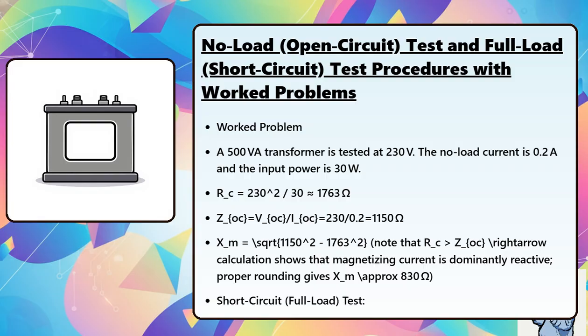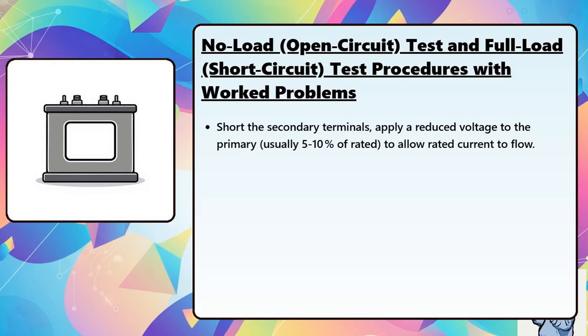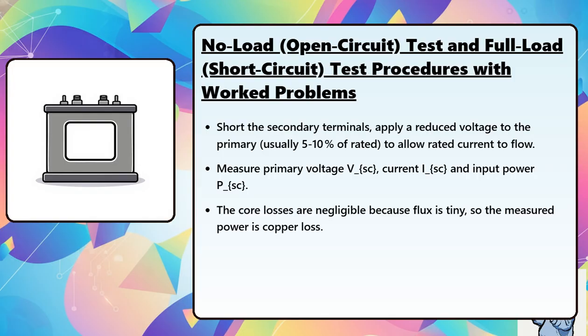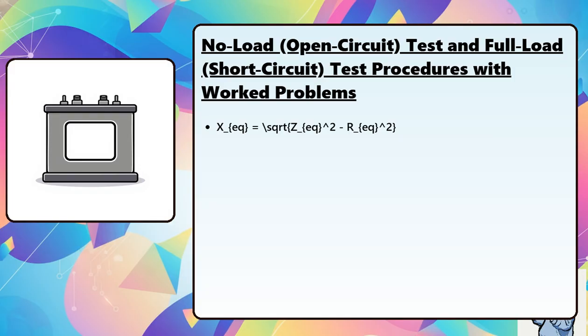Short circuit full load test. Short the secondary terminals, apply a reduced voltage to the primary, usually 5 to 10% of rated, to allow rated current to flow. Measure primary voltage V sub SC, current I sub SC, and input power P sub SC. The core losses are negligible because flux is tiny, so the measured power is copper loss. Parameters: R sub EQ equals P sub SC divided by I sub SC squared. Z sub EQ equals V sub SC divided by I sub SC. X sub EQ equals the square root of Z sub EQ squared minus R sub EQ squared.